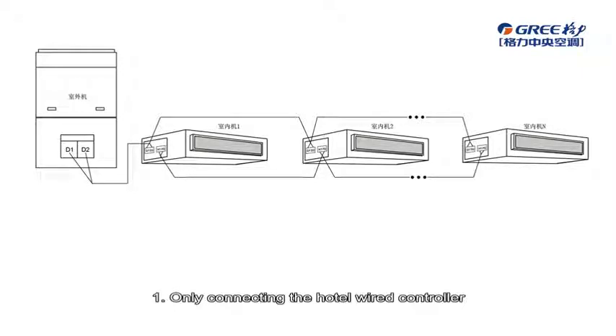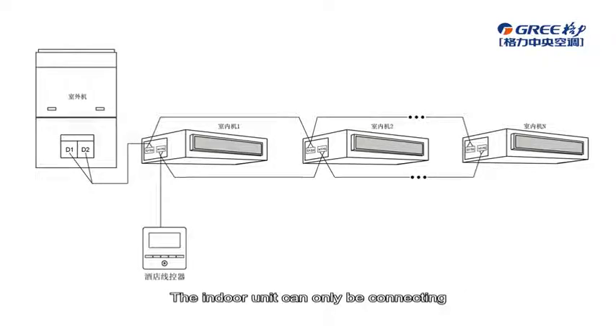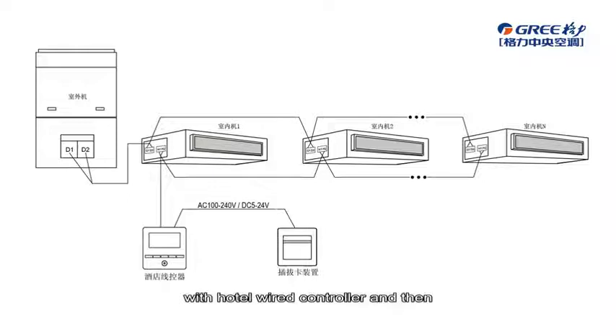First, only connecting the hotel wire controller. The indoor unit can only be connected with hotel wire controller and then the hotel wire controller is connected with door control system. In this case, the unit can be turned on or off by inserting or removing the keycard.